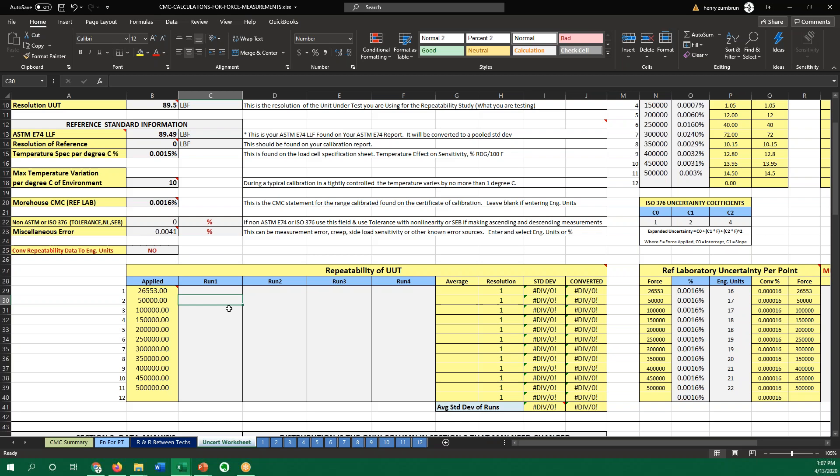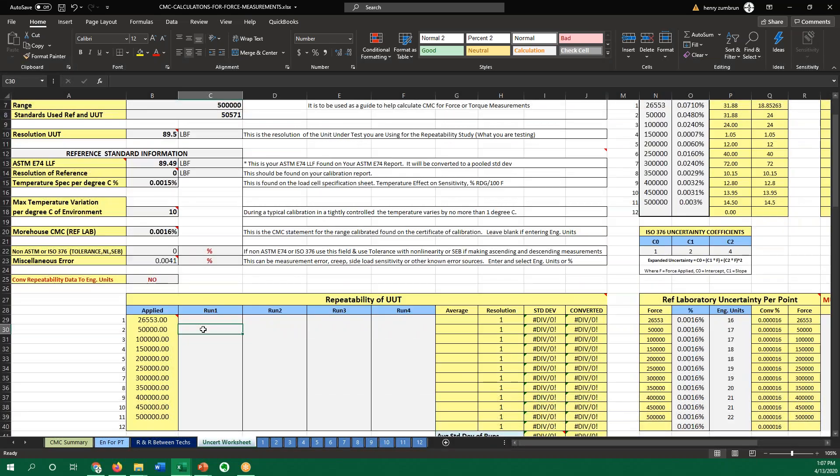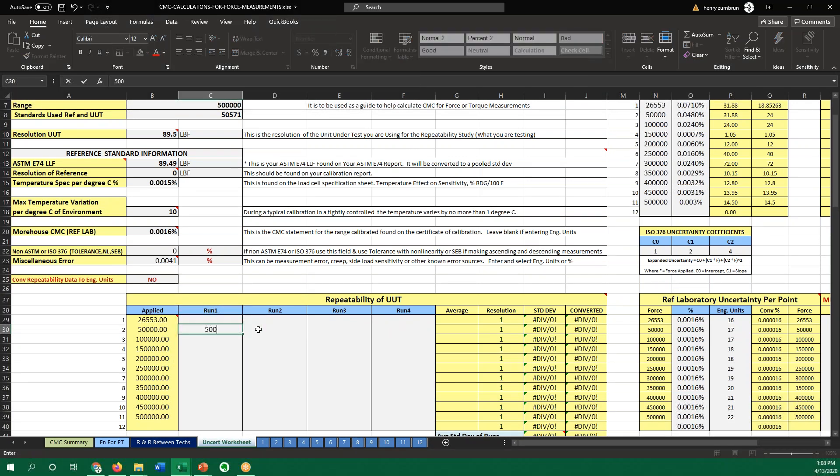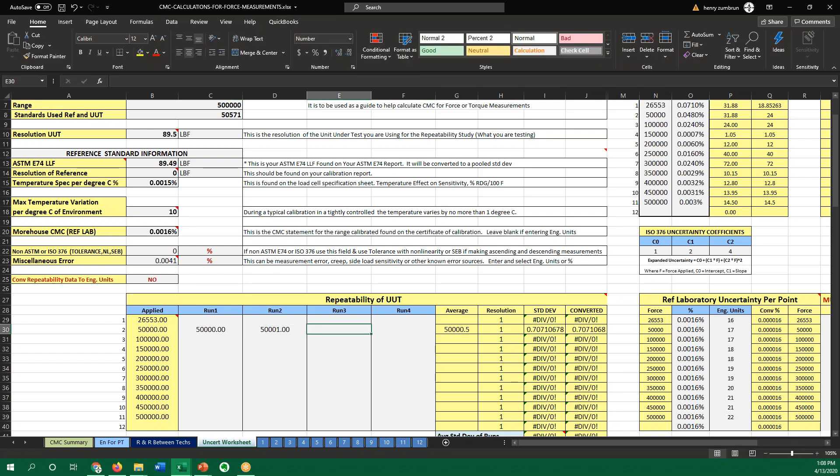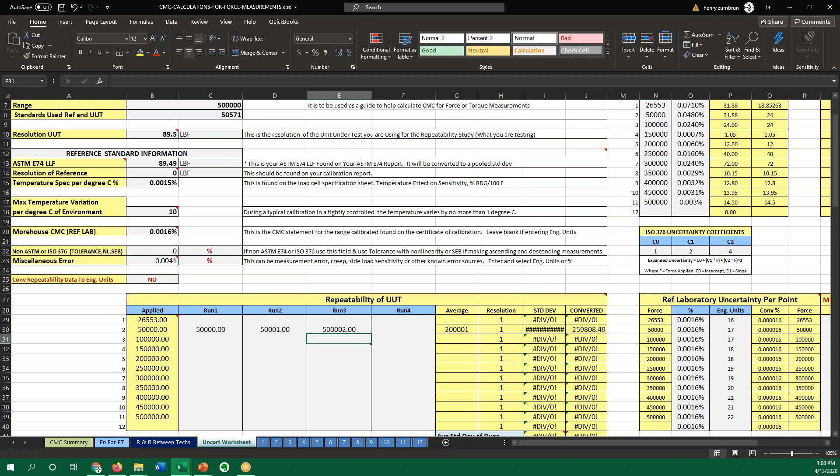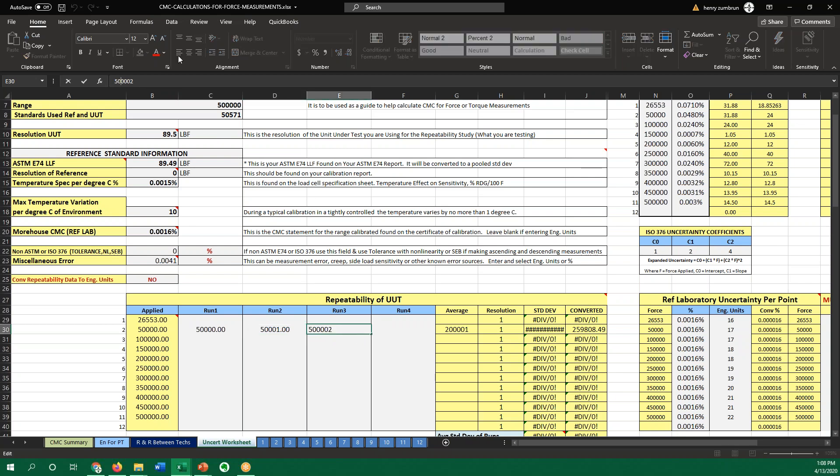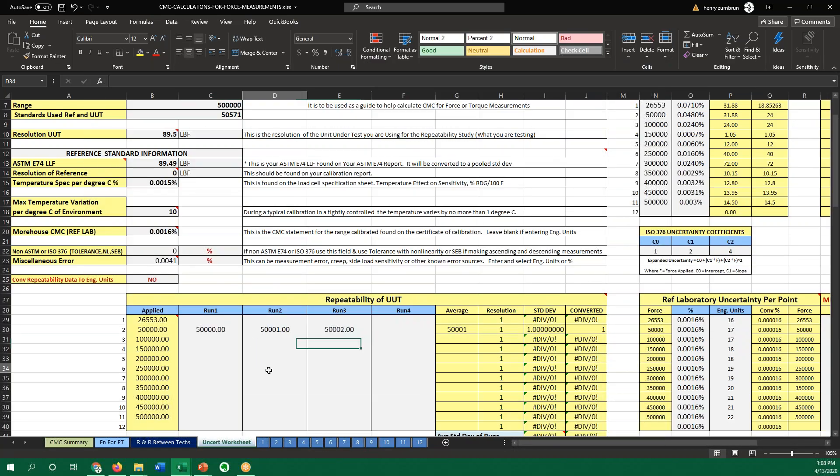You're dealing with more than just one number if you're dealing with force. In this situation, we have a half-million-pound device. We could go in and we could do repeatability per point, which is you just enter the numbers in here. And we can look at this sheet then, 50,000, 50,001, 50,002. So in this case, we have 50,001, we have 500,000, put too many zeros in.